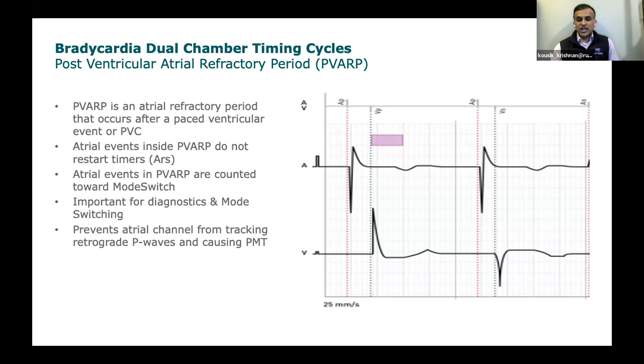But if the device doesn't have an auto feature to do that, the way that you would do it is either put a magnet on the device, which then switches it to a DOO mode, or you interrogate the device and you can manually extend the PVARP so that you can make that retrograde atrial activation be blind and the atrial lead won't see it any longer.